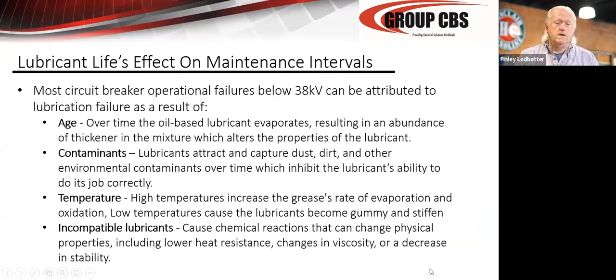There we go. We talked about this already, but lubricant is really the lifeblood of the breaker, and that's where most of the errors come from. It ages and thickens with time. Don't let it be mixed or contaminated with other lubricants, because the bases in the lubricants will attack each other. There's chemical reactions and hardening that takes place, and it's just catastrophic to the breaker. So be sure your maintenance company understands what's in the breaker and they use the same lubricant.